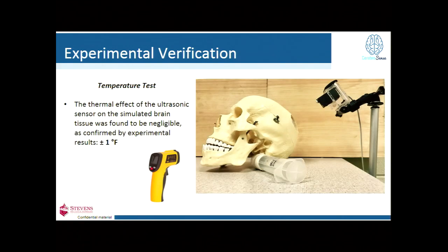And the other test that we performed is a temperature test, which we did in order to show that the sensor is actually harmless when we're exposing the surface of the brain. So in this case, we were able to measure the temperature difference after leaving the sensor applied to the surface of the balloon for a certain period of time. And we also saw successful results in this experiment because we saw a variation of less than 1 degree in this case.